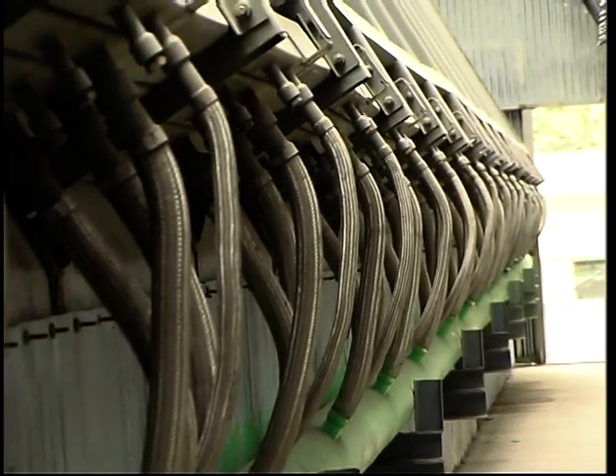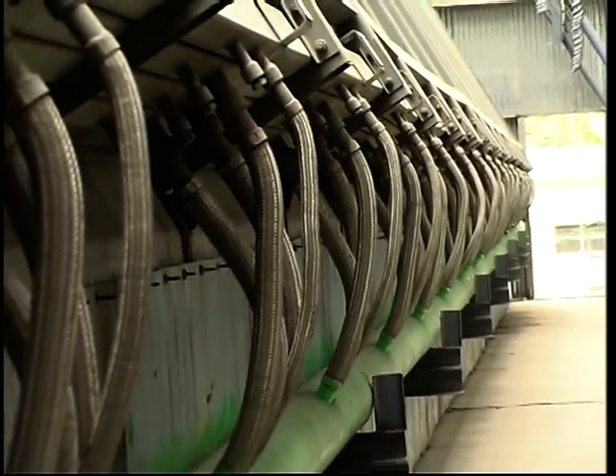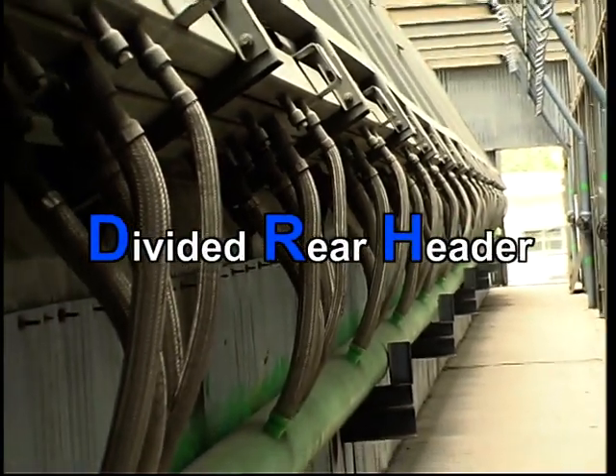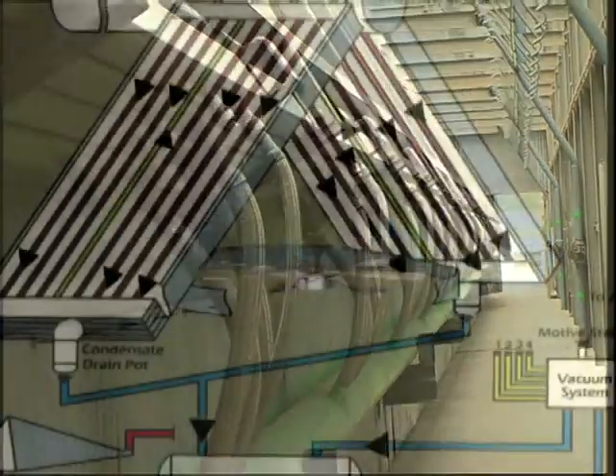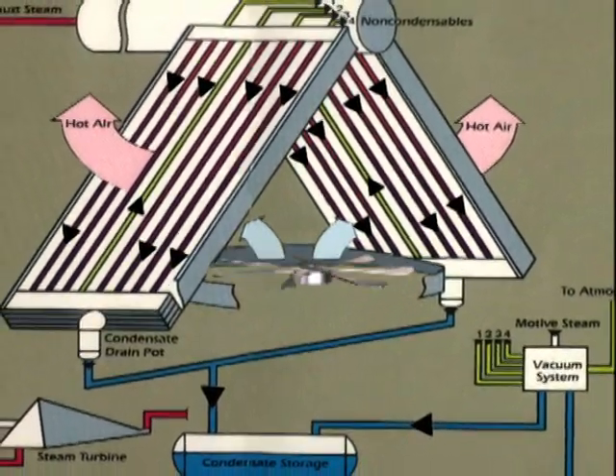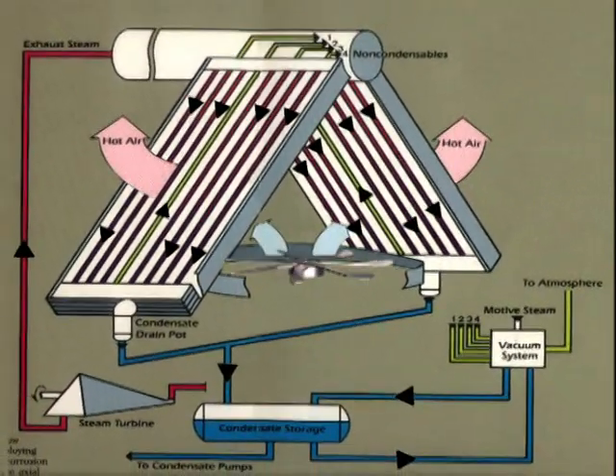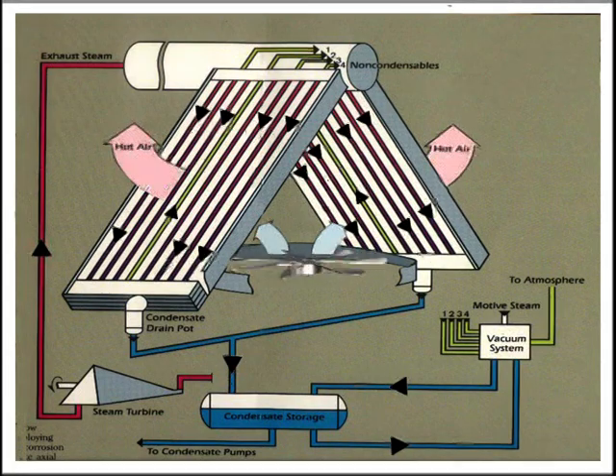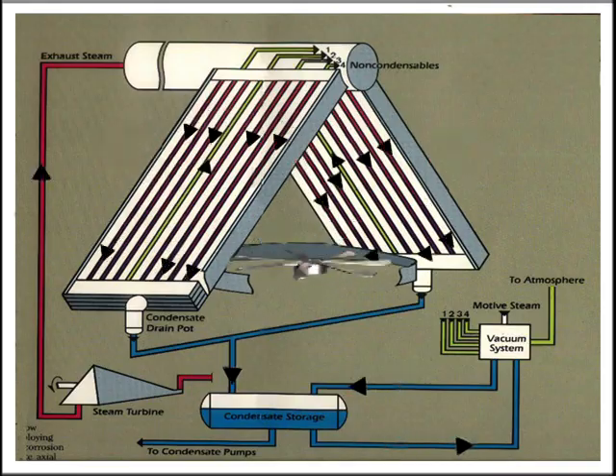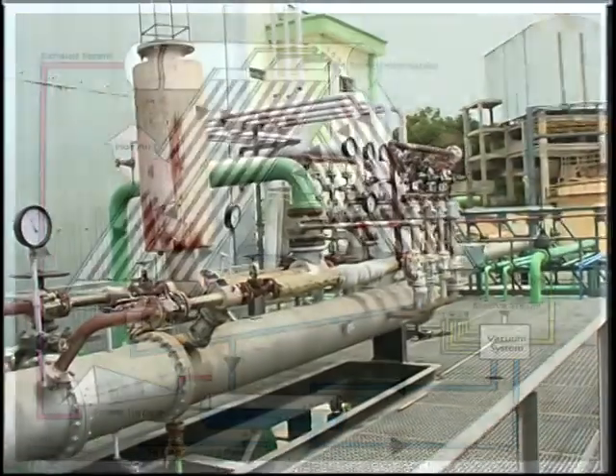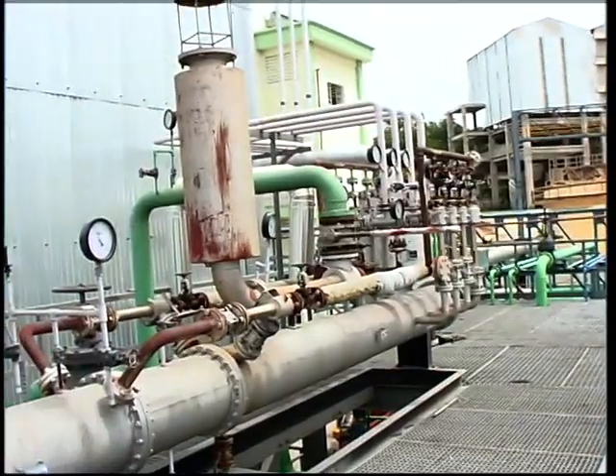A unique feature of the Paharpur air-cooled steam condenser is its divided rear header or DRH design. In a typical A-frame type steam condenser, steam routed through the turbine exhaust duct enters the condenser bundles at the top and the condensate flows out through the lower end. Non-condensables are vented out of each row of the condenser using individual steam jet air ejectors or vacuum pumps.